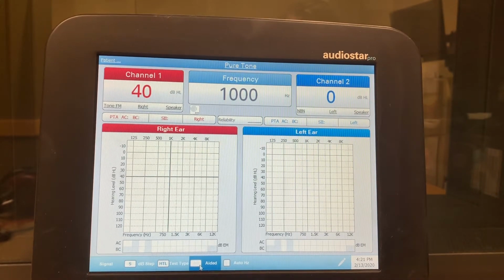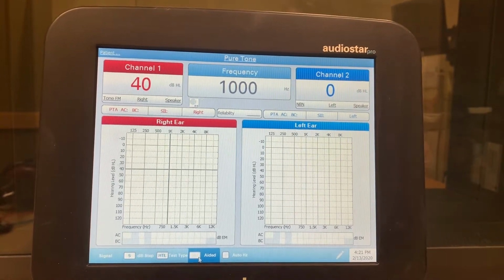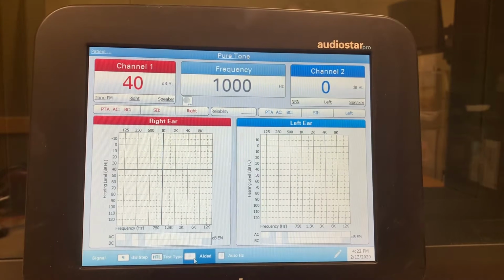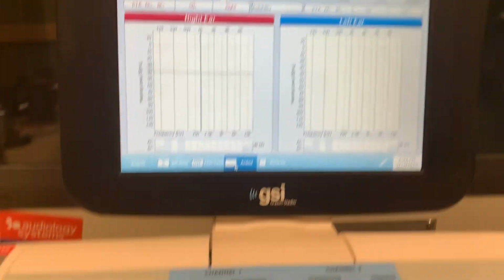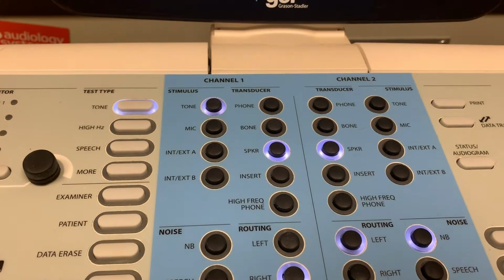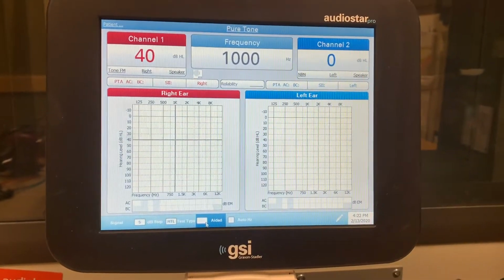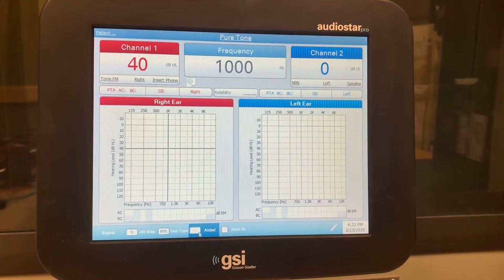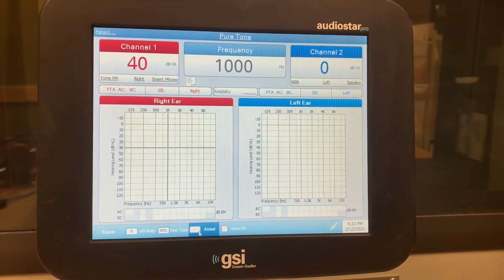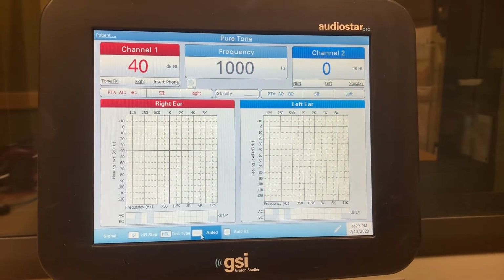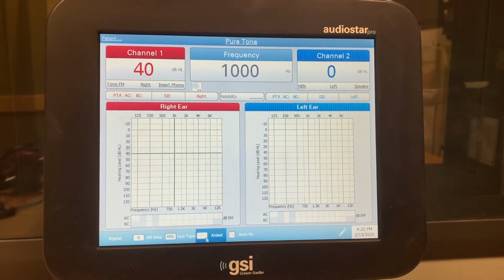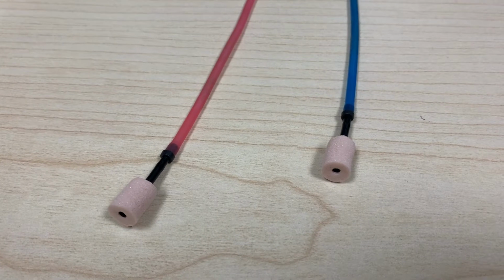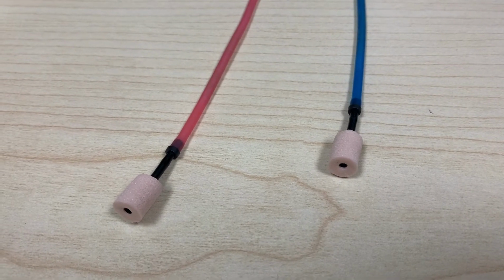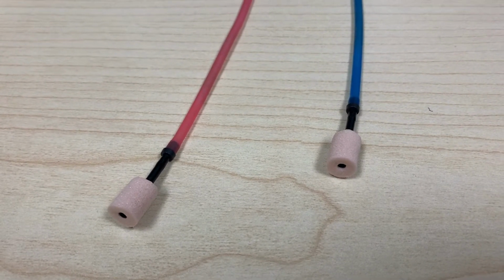Perfect. And for some reason, when we clicked aided, did you notice the transducer switched? So now it says speaker. We need to go back to insert phone. So you always want to be mindful of what your screen is telling you so you have the most accurate results. So when you're testing someone who doesn't use hearing aids, best practice is to use insert earphones.